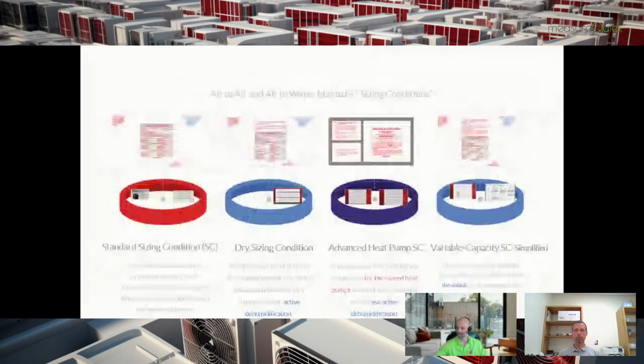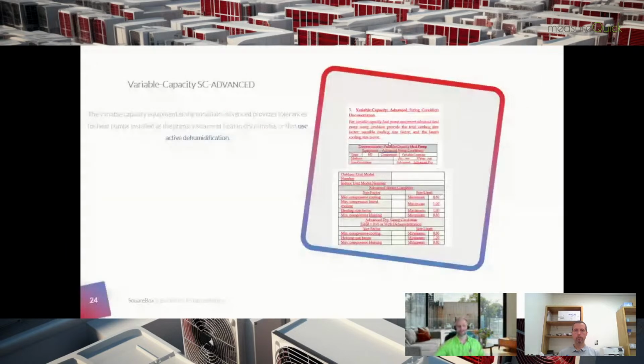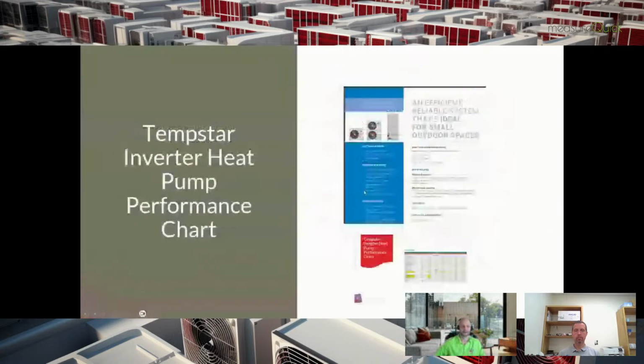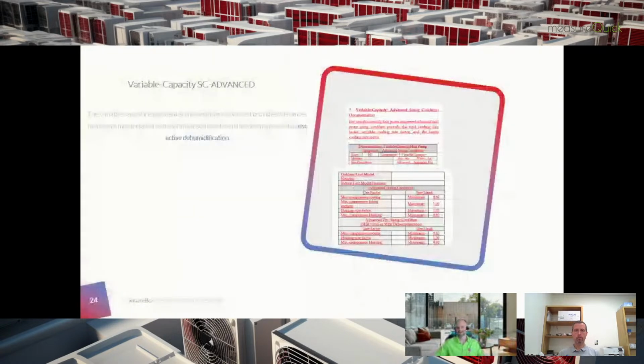And then the last one is variable capacity advanced, which is the most advanced way that you can size. It allows you to, what I was just talking about, find a balance point between heating and cooling and use minimal resistance backup heat, or none, as possible. The ideal is to try to get the backup heat out of there.